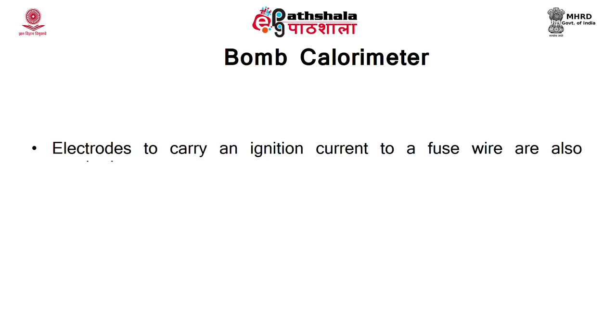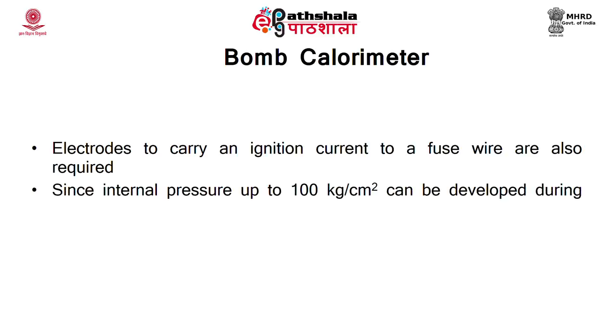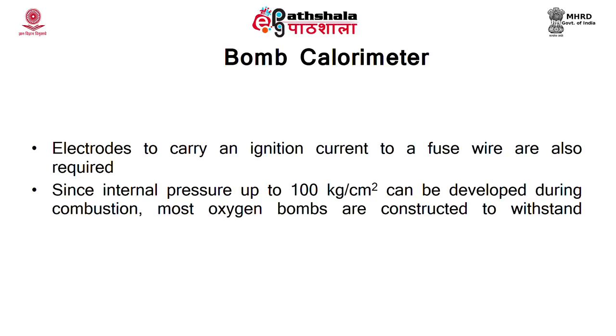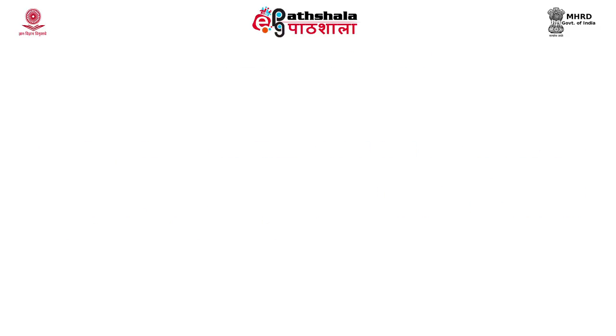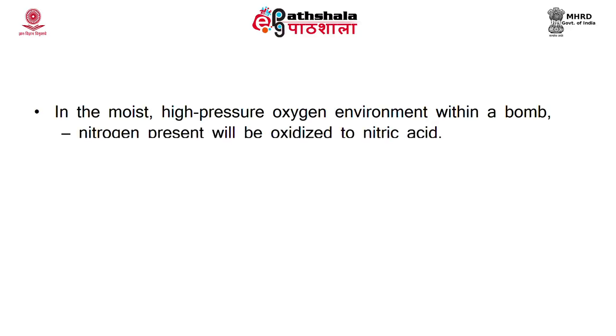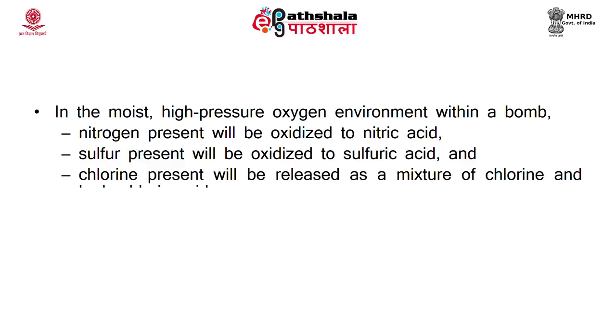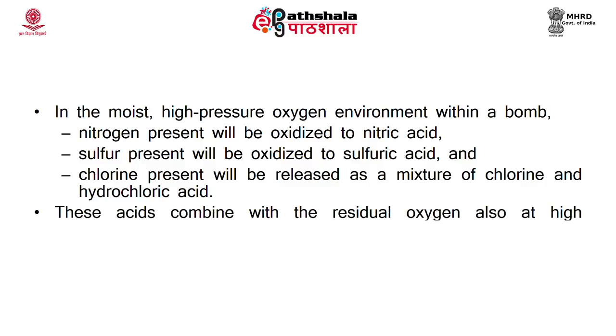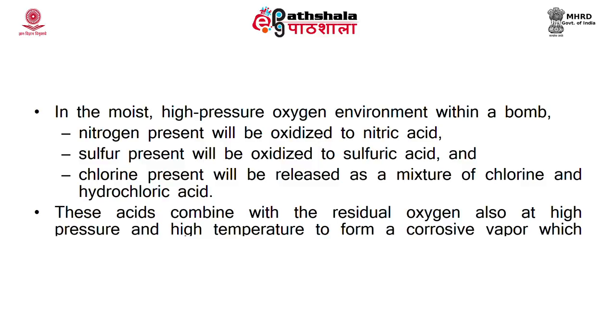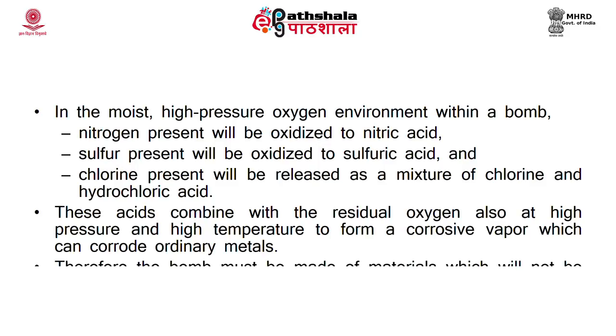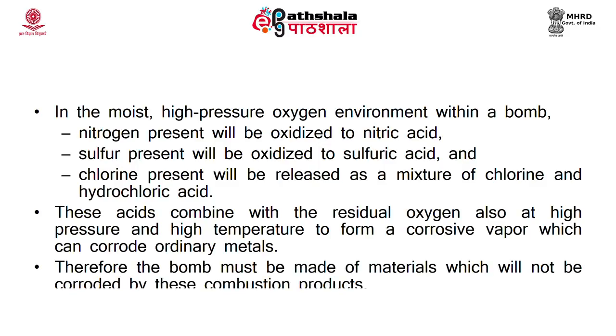Valves are provided for filling the bomb with oxygen under pressure and for releasing residual gases at completion of the experiment. Electrodes to carry ignition current to a fuse wire are also required. Since internal pressure up to 100 kg/cm² can develop during combustion, most bombs are constructed to withstand pressures up to 200 kg/cm². In the high-pressure oxygen environment within the bomb, nitrogen is oxidized to nitric acid, sulfur to sulfuric acid, and chlorine is released as a mixture of chlorine and hydrochloric acid. Therefore the bomb must be made of materials not corroded by these combustion products.